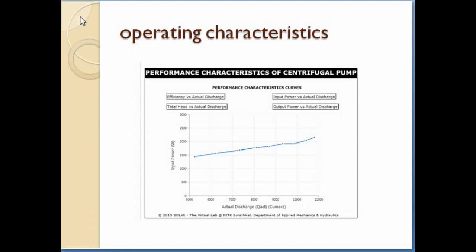On the screen, we can see the first graph, that is input power versus actual discharge. Here along the x-axis actual discharge is plotted, along the y-axis input power is plotted. What we can observe is that with higher discharge values, the power consumed by the pump, or the input power supply, is also more.